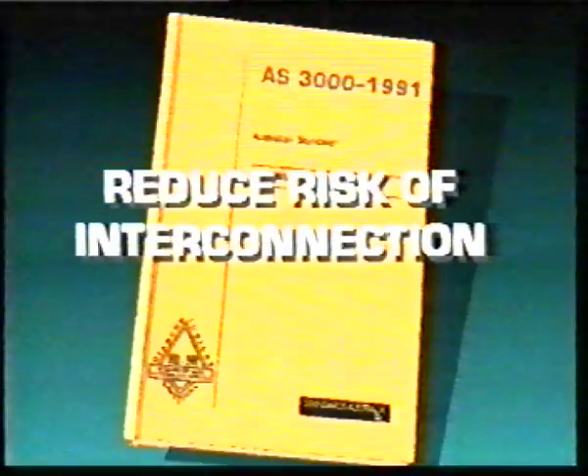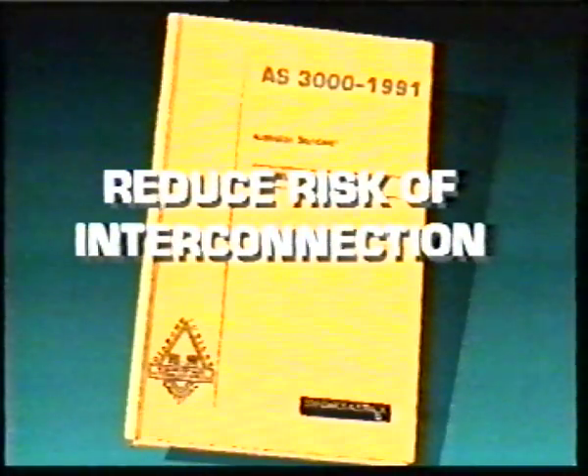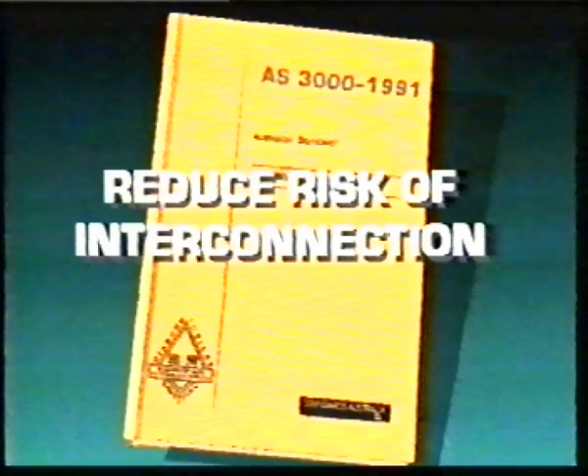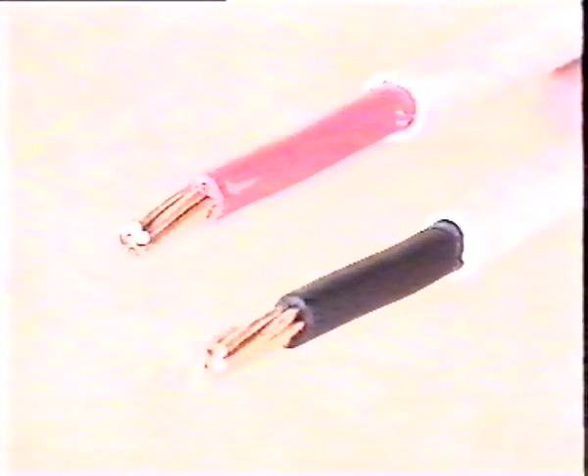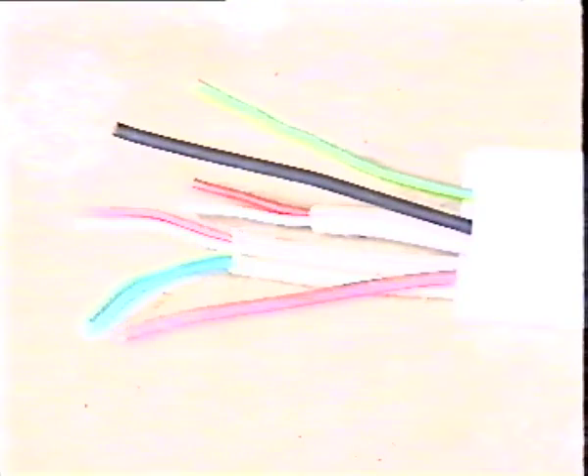This condition may occur between circuits of the same installation or between different installations, for instance, multiple occupancy premises, such as shopping centres. Again, AS3000 generally requires a number of practices to be observed which reduce the risk of interconnection occurring. These practices include the sheathing of cables of consumers' mains or cables of different installations where they share an enclosure with other cables. Segregation is to be maintained between different systems, for example, low and extra low voltage, and testing should confirm that the wiring of each circuit is independent from that of other circuits.